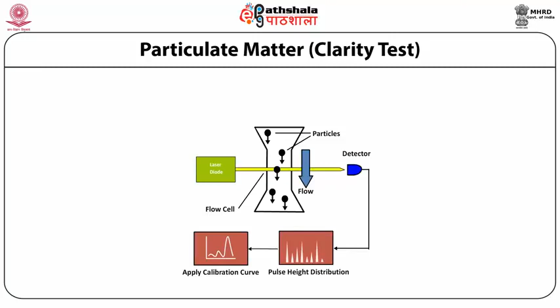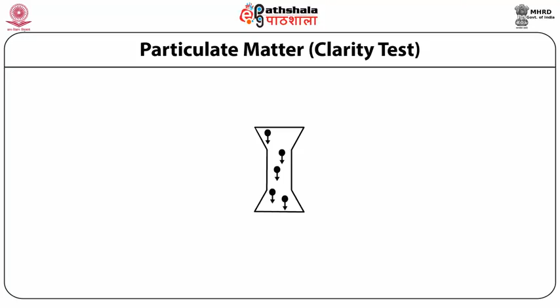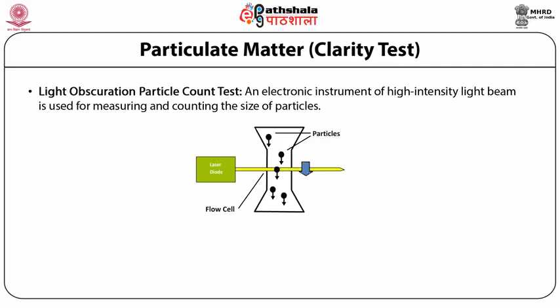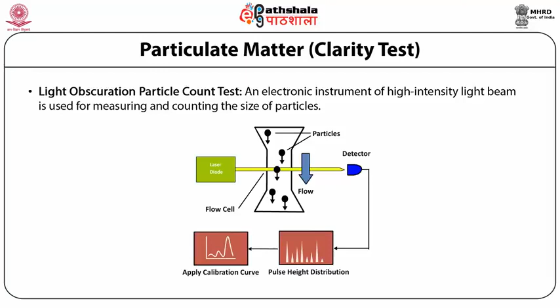There are some methods for determination of the particulate material present in parenteral preparations. The first one is the light obscuration particle count test. This is an electronic instrument in which a high intensity light beam is used for measuring and counting the size of the particles. The diagram shows a high intensity light passed through the cell in which the preparation is tested, and some light is reflected onto the detector, which shows whether particles are suspended in the formulation or not. If no sensitivity is shown by the detector, the preparation is free from particulate material and the test is passed.